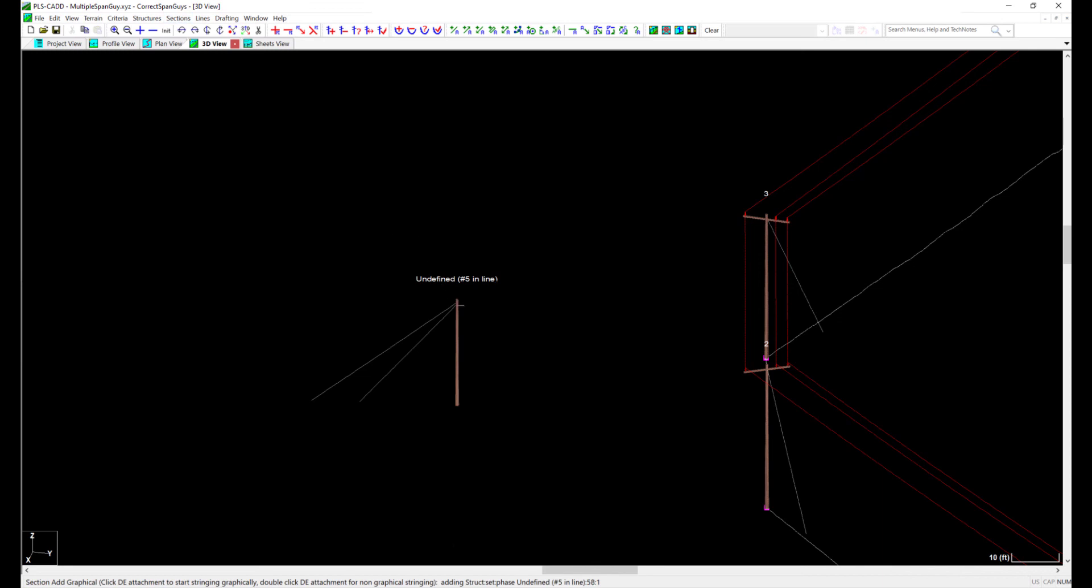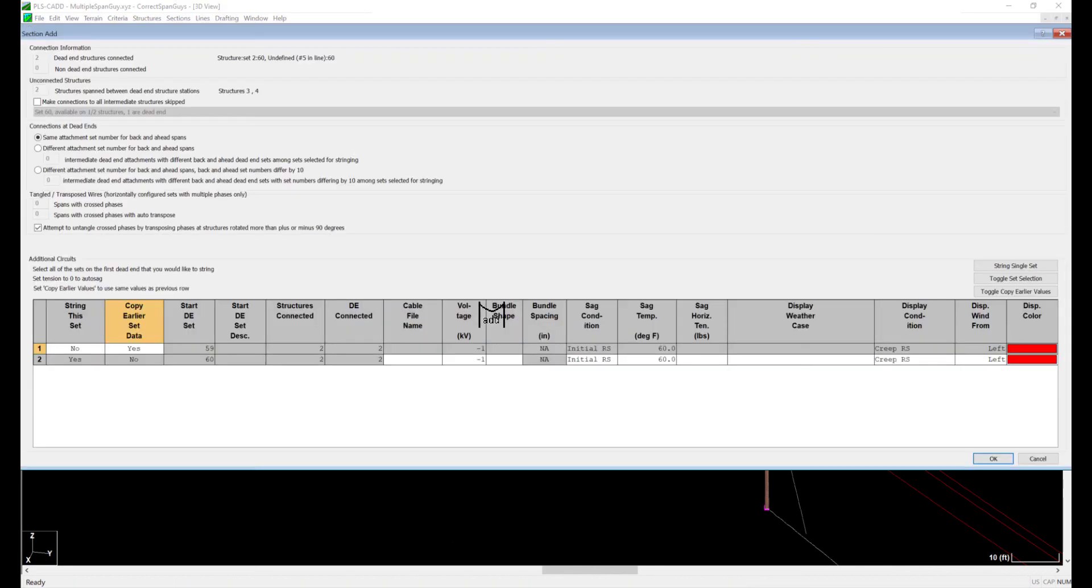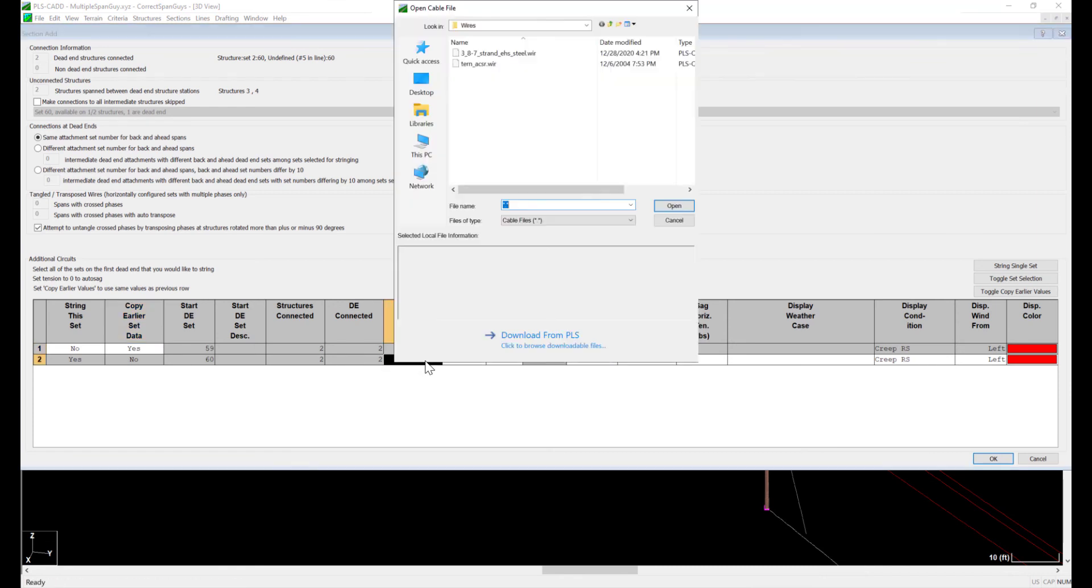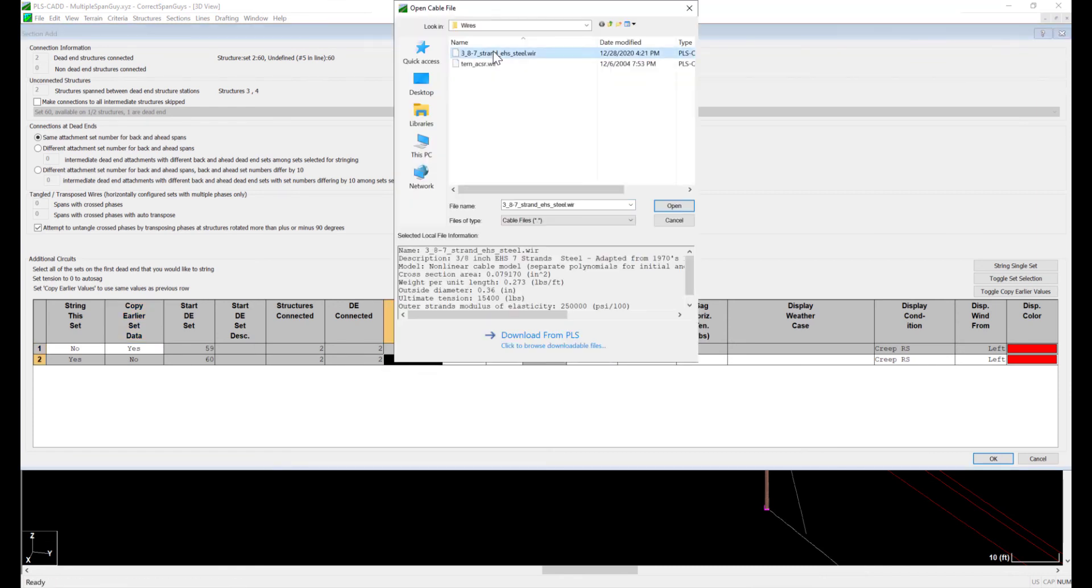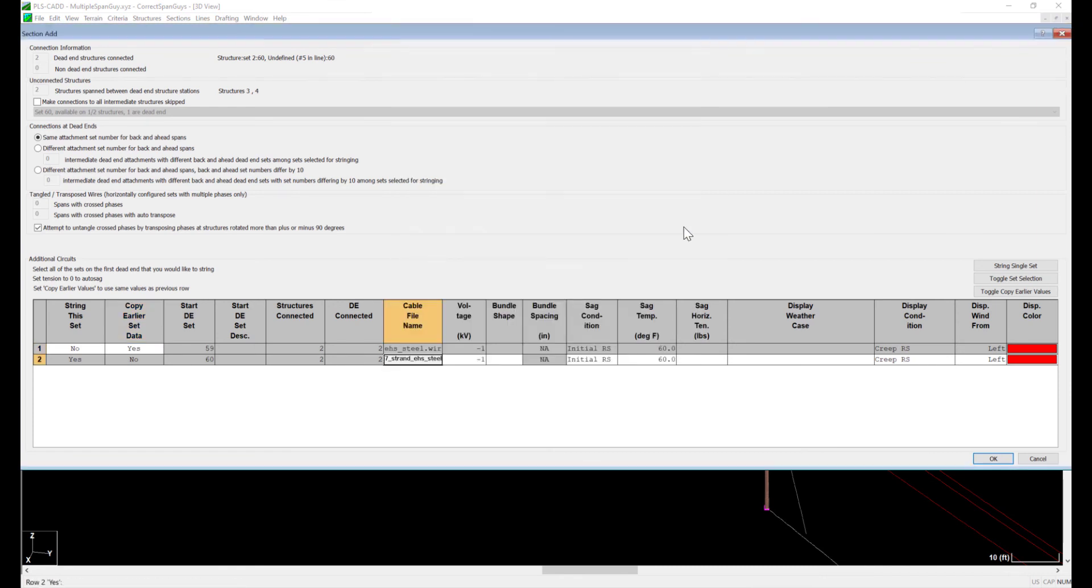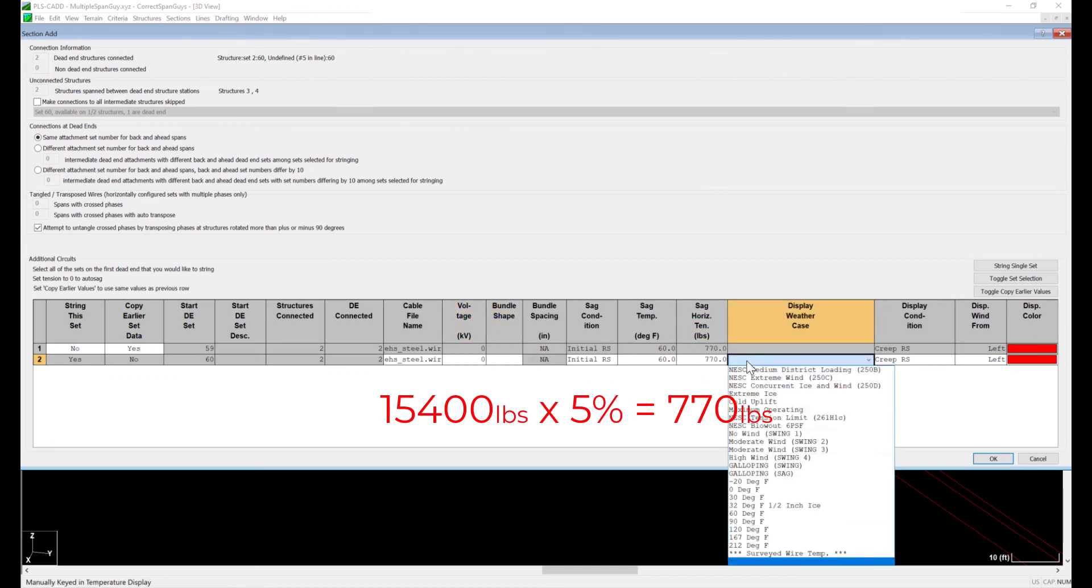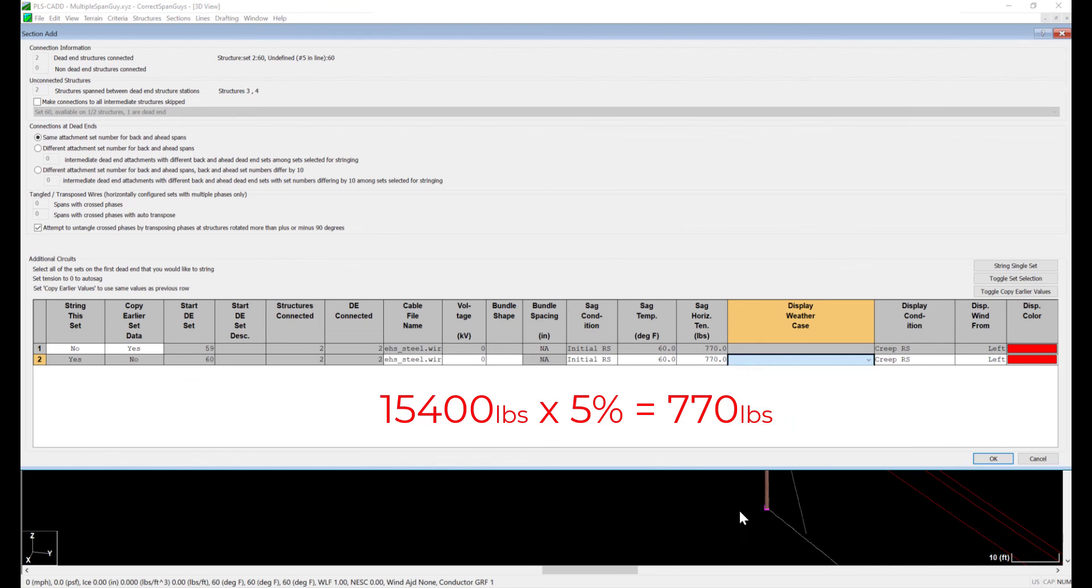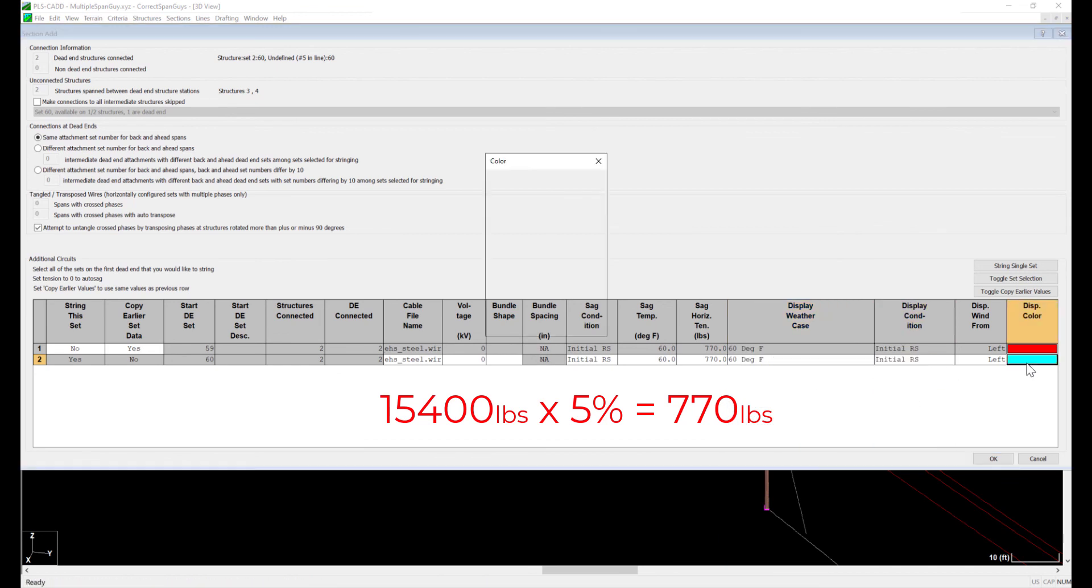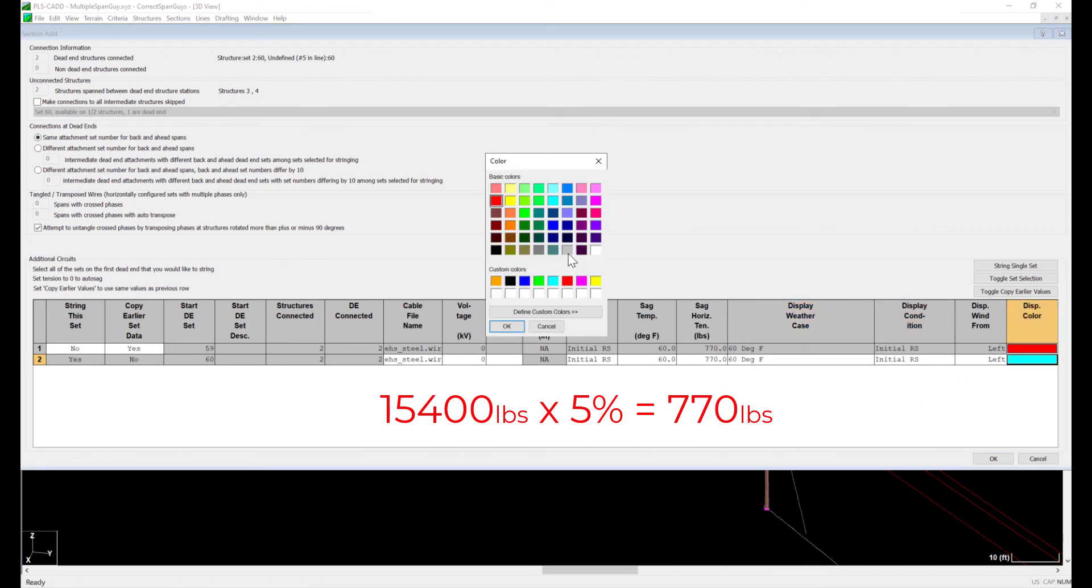I'll use a typical 60 degree initial stringing case, and I'll add my same 3/8 inch steel shield wire that I was planning to use for my span guys. For my install tension, I use 5% of the rated breaking strength for span guys in PLS CAD. This equates to 770 pounds, which I'll put in my stringing tension.